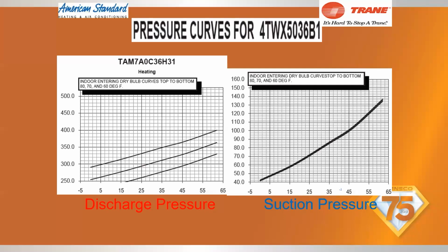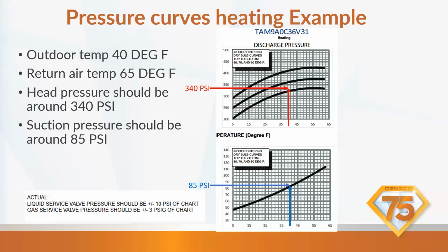Here's a single stage 5036. So this one's a 15 SEER 3-ton. So same thing, you got your discharge pressure on this side. That's where you got to get it close. It works. And the question is, does the chart change with different coil matchups? So these are out in the outdoor unit. You can see this one's a TAM 7. This one's working with the TAM 9. So again, that's why I'm saying use these charts and get them close. This is for the outdoor unit, but the coils will change up your pressures just slightly. That's why we're just getting them close. That's why the best charging method is to get that 10 degrees subcool during a warmer climate.